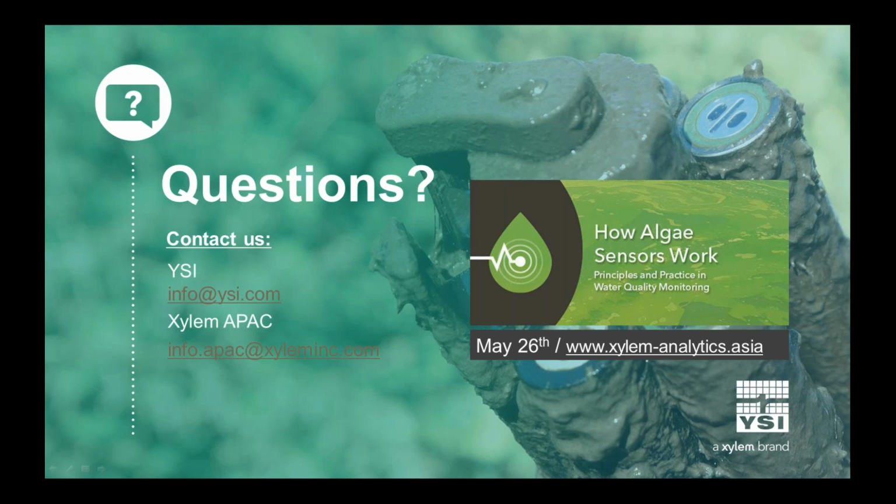Real quickly, Michael, I'd like to add a little bit to that. When you get back to the lab, when you're transporting your handheld and sensors back and forth between your collection site and the lab, take a minute to wash out and clean that sensor guard, because typically you're going to store those sensors moist with a little bit of solution in the bottom of your transportation cup. And if you bring water from the estuary or wherever you're sampling back in, and then you put that up on the shelf and go out the following week, that's where you're likely to see some buildup on those sensor faces. It's just from the growth that can occur while you have it in storage. So just make sure that you clean everything up really well before you put things away between your next visit.